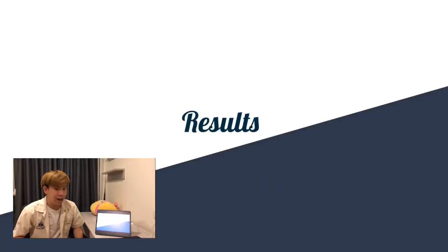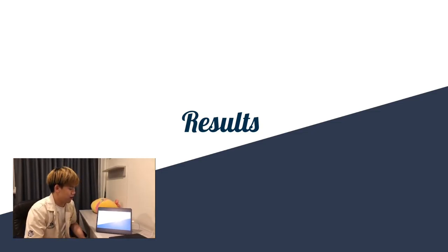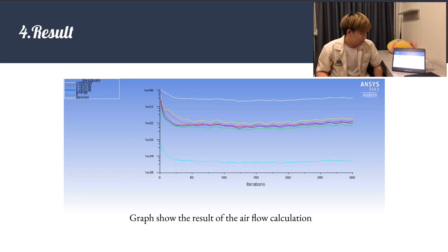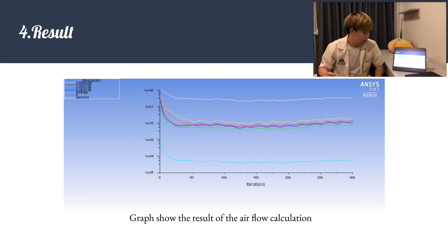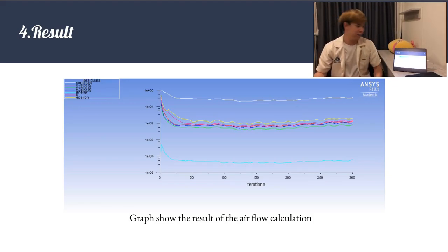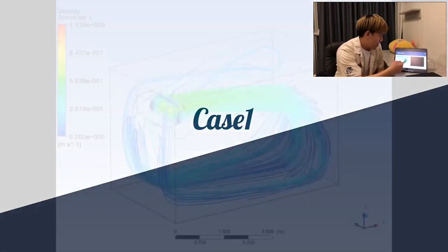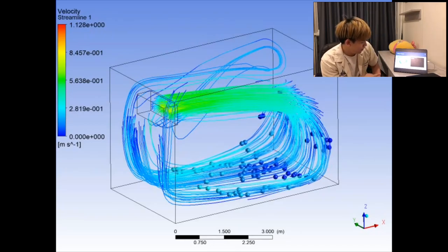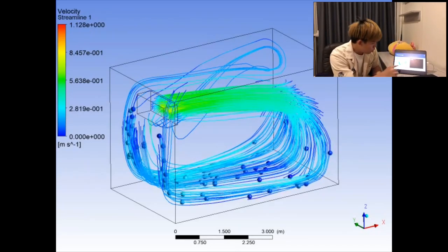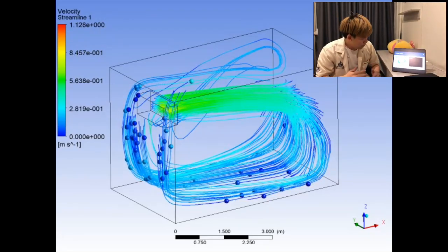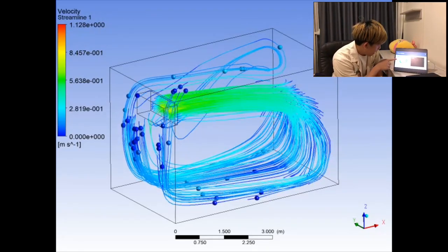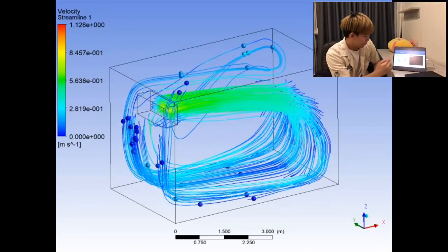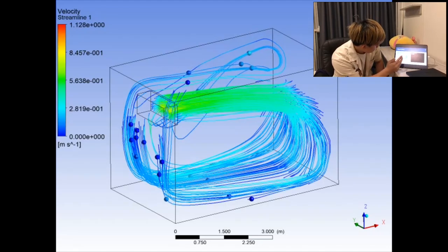After the setup, we computed the solution. The residual graph trends steadily downward until reaching steady state. For Case 1 with one air conditioner, the flow moves forward with high velocity toward the edge of the room, but cannot cover the entire room. The streamlines show a circular motion without much airspeed in the middle of the room.